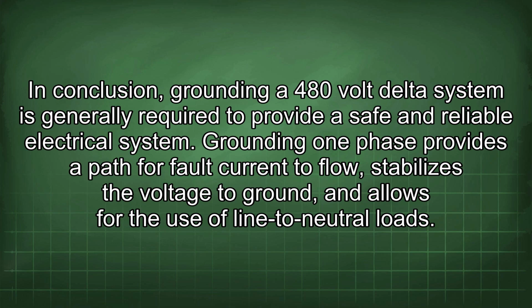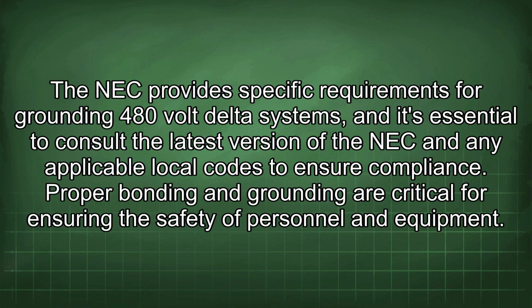system. In conclusion, grounding a 480-volt delta system is generally required to provide a safe and reliable electrical system. Grounding one phase provides a path for fault current to flow, stabilizes the voltage to ground, and allows for the use of line to neutral loads. The NEC provides specific requirements for grounding 480-volt delta systems, and it's essential to consult the latest version of the NEC and any applicable local codes to ensure compliance. Proper bonding and grounding are critical for ensuring the safety of personnel and equipment.